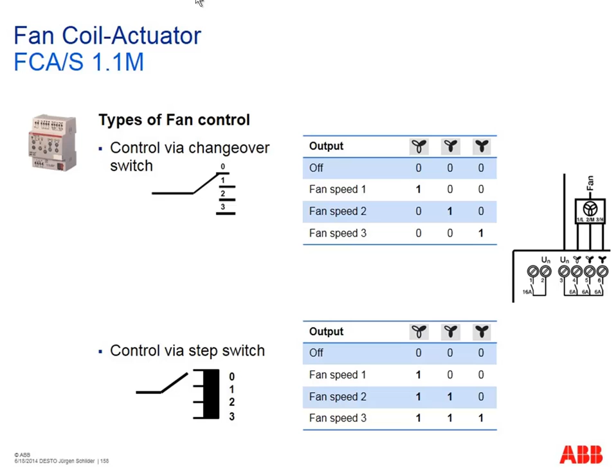Or do we have a motor which works on the principle of a step switch? Then you can see the difference. Fan speed number 1, only the first output is closed. Fan speed number 2, the first and the second. Fan speed number 3, the first, the second and the third output are closed. So it is very important to read the manual, the technical data sheet of the motor, to see which principle the motor works on, and use the correct settings inside the ETS parameters.